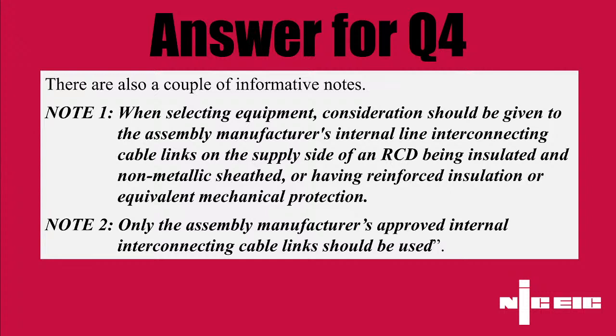When we do a periodic inspection, do we do it against the current regs, or do we do it against the regs that we believe the installation was designed and installed to, Dan? What's our first thoughts on that? They're not retrospective. That's what I have to say. We get this asked quite a lot, don't we, Sam, to be fair? So they're not retrospective. When we are looking at an installation, you're looking at the time it was installed, obviously, what was in the regulations at the time. So I think the only time you might find a crossover, though, is where you've got outdoor socket outlets which aren't on an RCD. I think that's probably one.